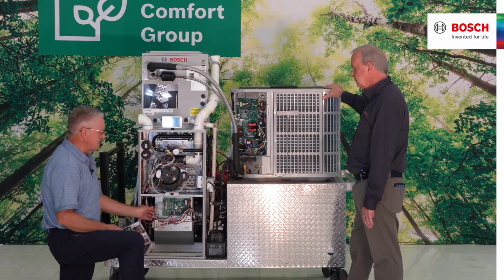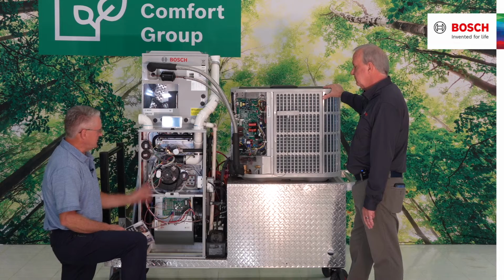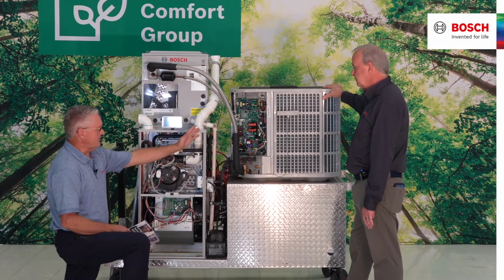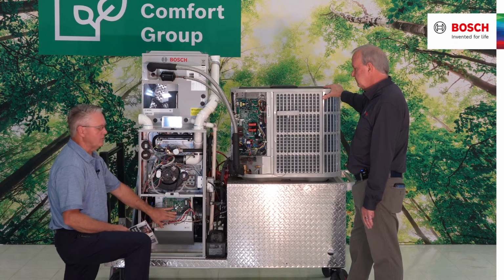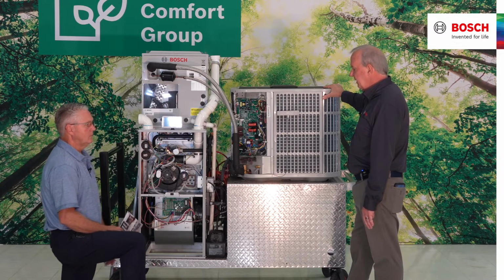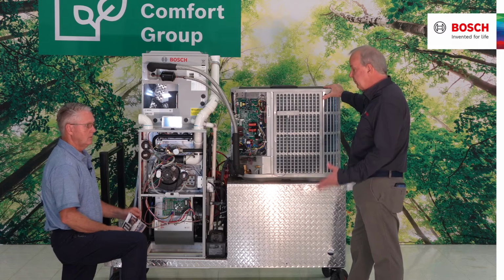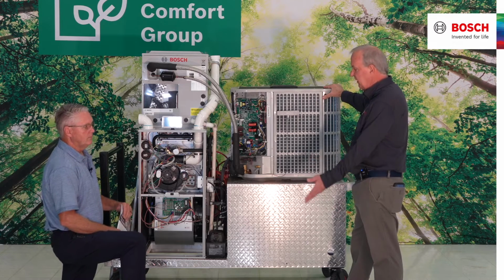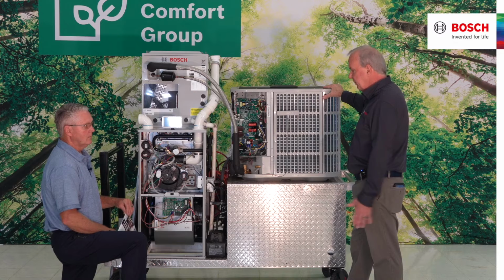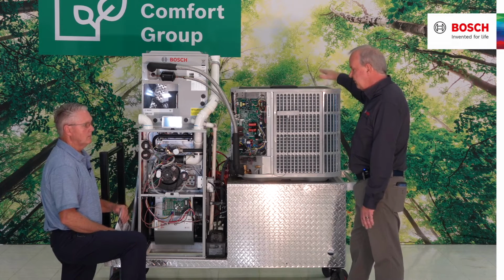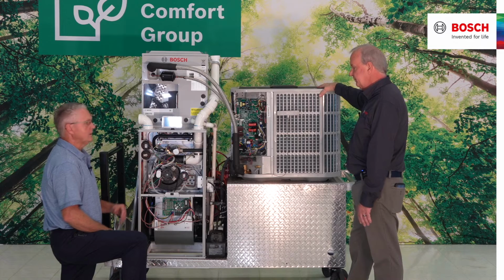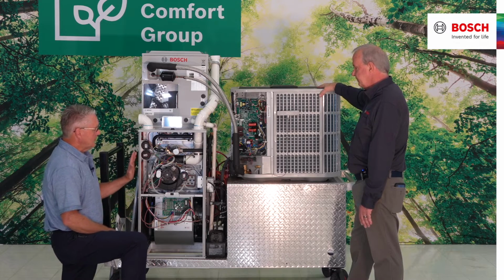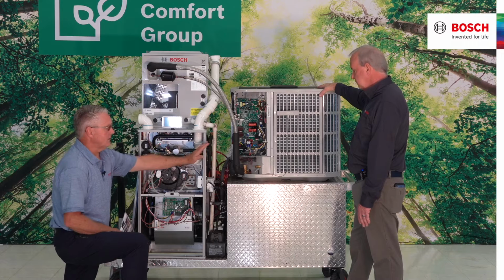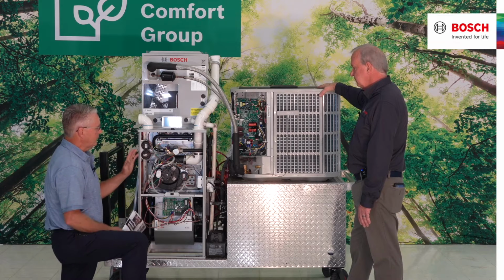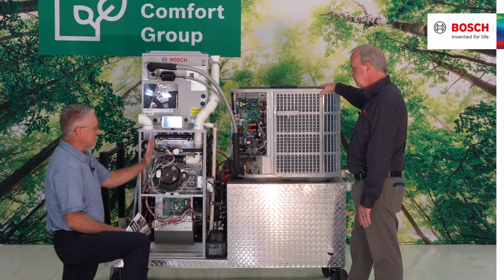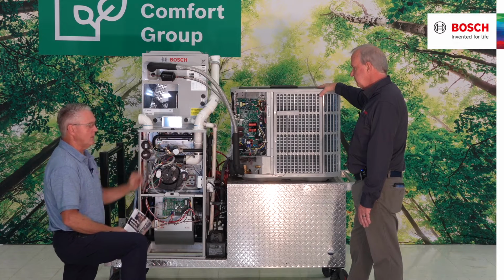So it is just a single wire nut that connects the thermostat to the outdoor unit and does not go through the board. And the B terminal would be for the heat pump cycle alone, when we're not using the gas furnace and we're running the heat pump only. B is energizing the reversing valve in the heating cycle. Absolutely, okay. So again, this could just be an air conditioner and we could run a gas-fired furnace. But if we're running it as a heat pump, then we're going to energize that reversing valve in the heating mode, okay? Correct.